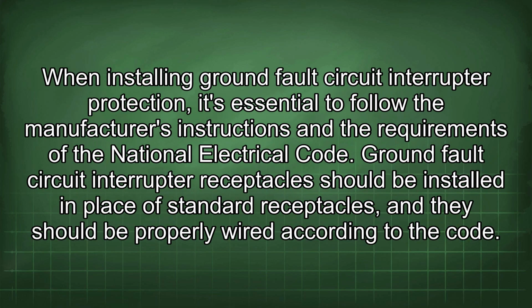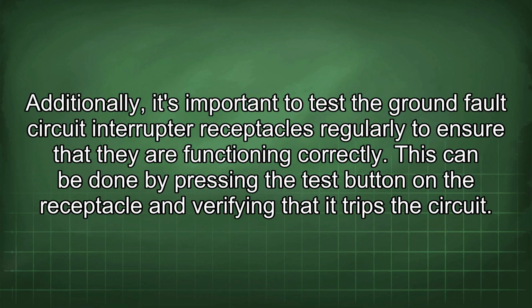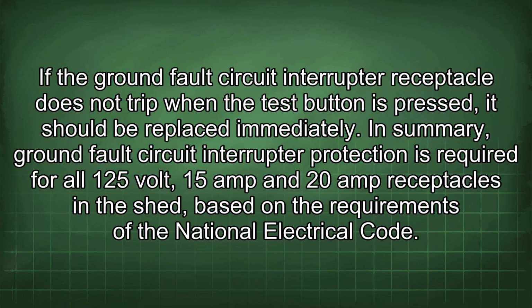When installing ground fault circuit interrupter protection, it's essential to follow the manufacturer's instructions and the requirements of the National Electrical Code. Ground fault circuit interrupter receptacles should be installed in place of standard receptacles, and they should be properly wired according to the code. Additionally, it's important to test the ground fault circuit interrupter receptacles regularly to ensure that they are functioning correctly. This can be done by pressing the test button on the receptacle and verifying that it trips the circuit. If the ground fault circuit interrupter receptacle does not trip when the test button is pressed, it should be replaced immediately.